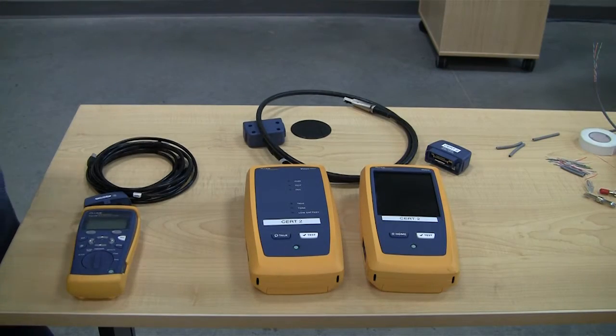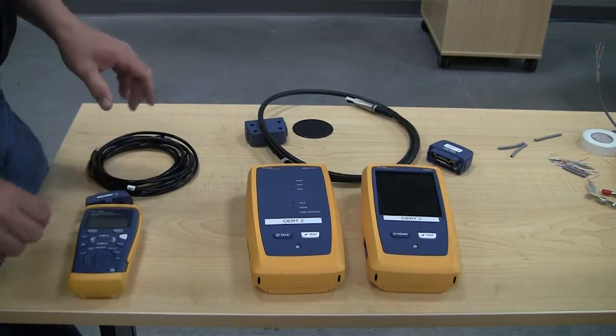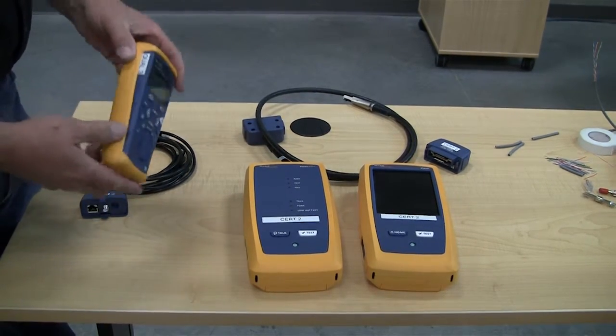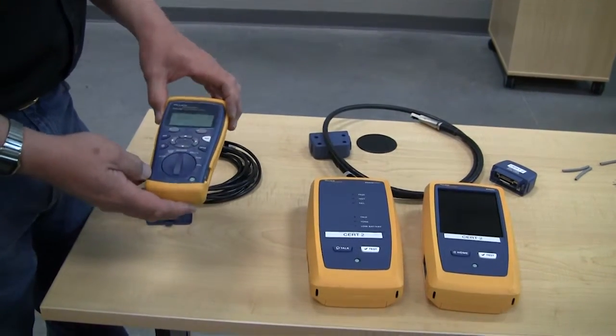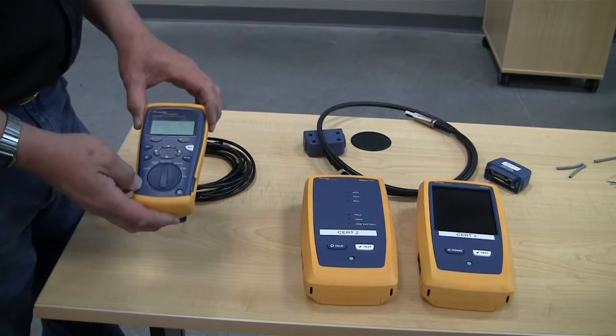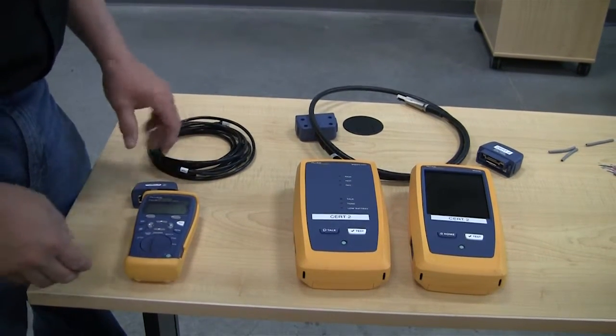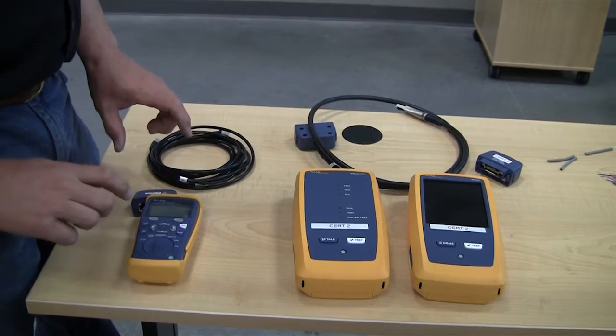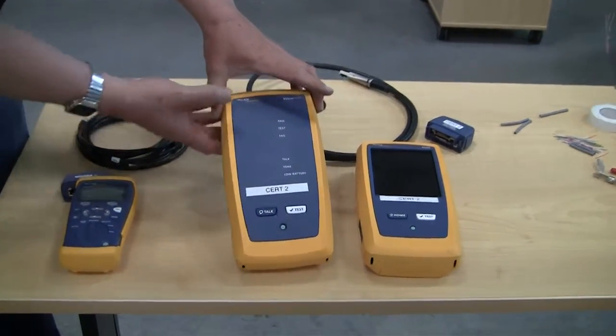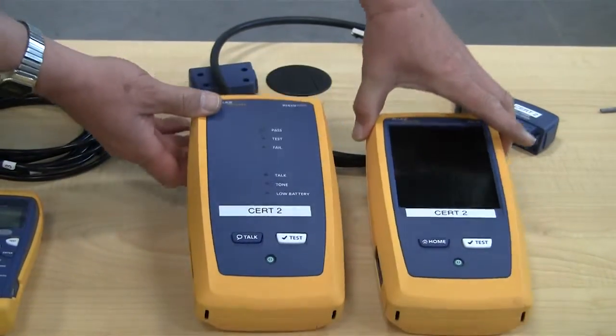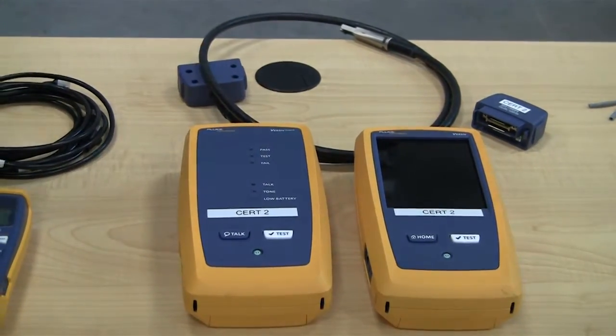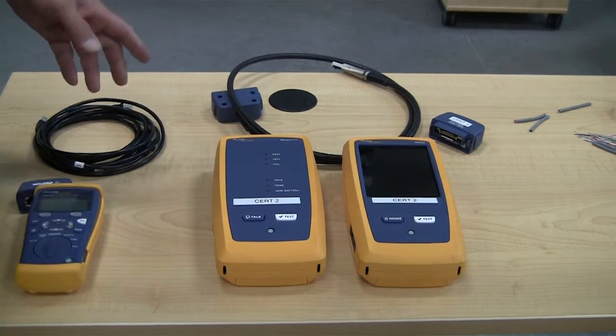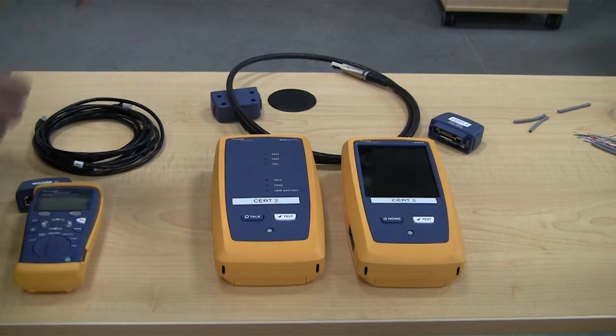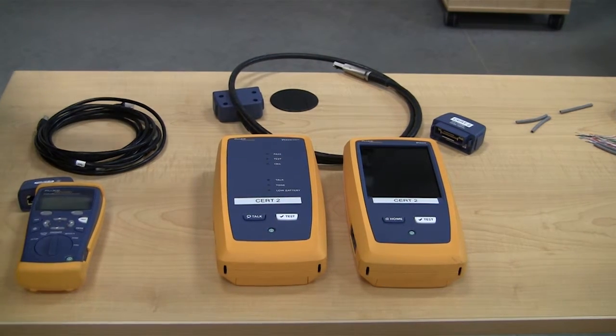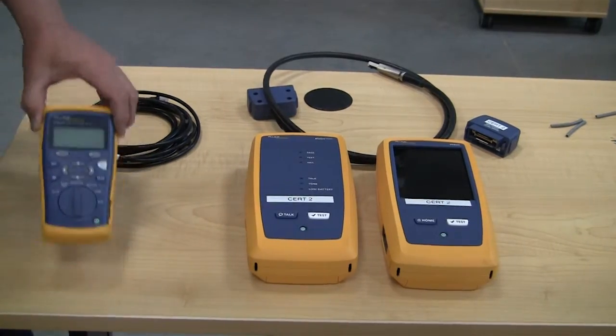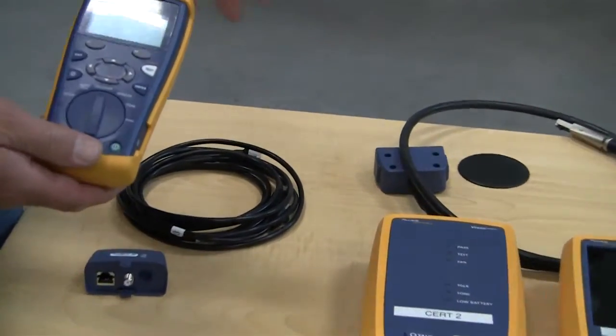We'll walk you through the test equipment. We've got two types we'll be using. One is called a qualifier, made by Fluke. It does wire mapping and tests the cable to tell you whether it's good or bad, but it doesn't do quite the job that the Certifier does. The Certifier is a two-part piece. We'll walk through the calibration on that, but it tests the cable to make sure it will do the speeds it was designed for, and that when you walk away it's up to the recommended standards.